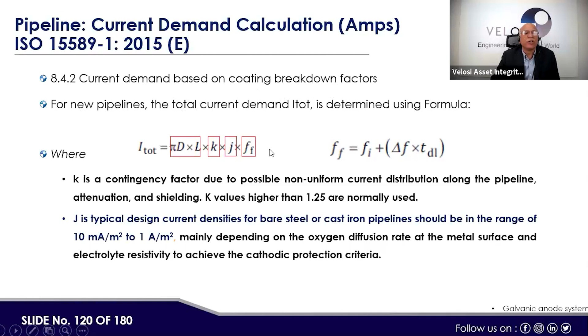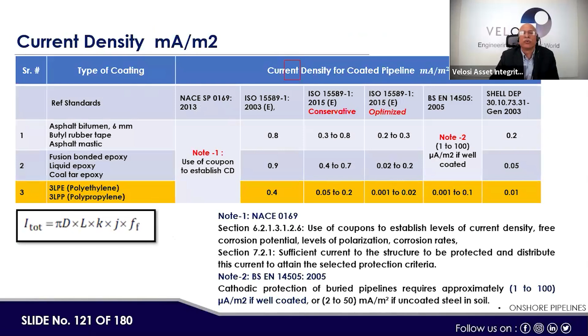Here is the current demand based on the coating breakdown. For a new pipeline, the total current demand is calculated this way. Then the total I is calculated based on the applicable factors. Here 0.4 is a factor as per ISO 15589-1:2003. Here we have an onshore pipeline, 24-inch diameter, 100 kilometers, 3-layer PE coated, for a 30-year design life.